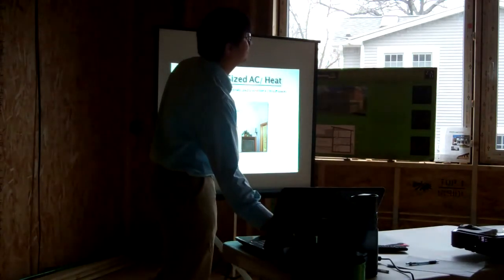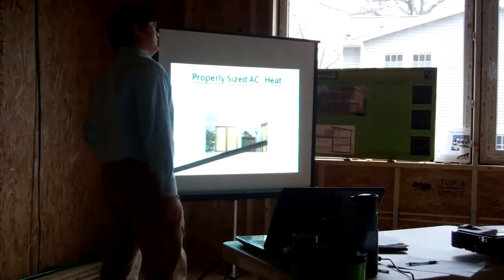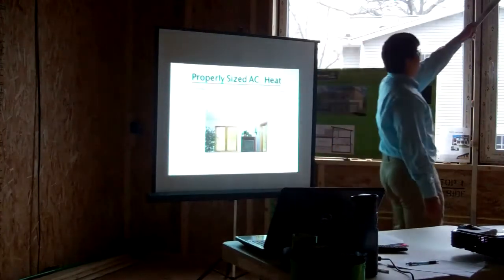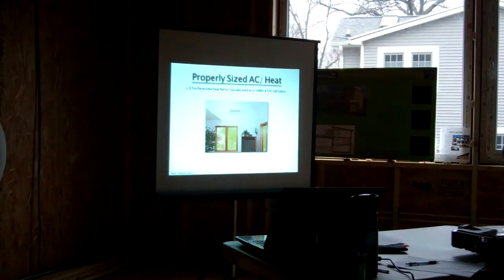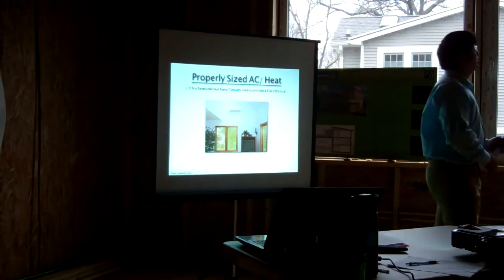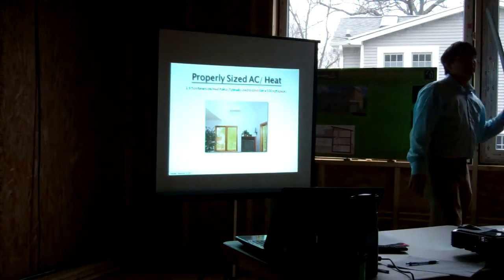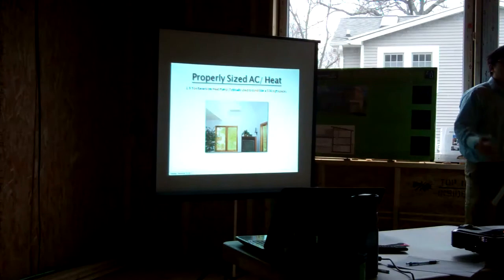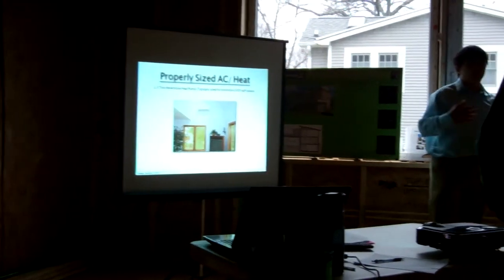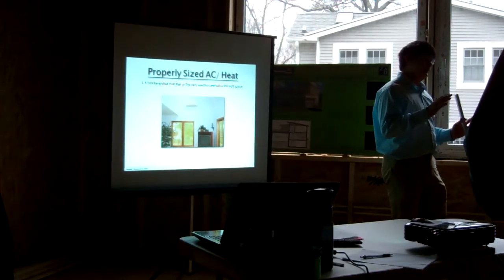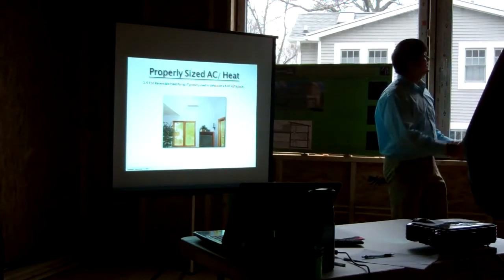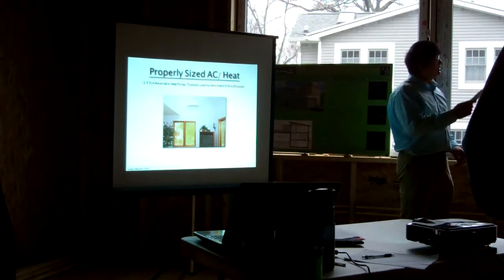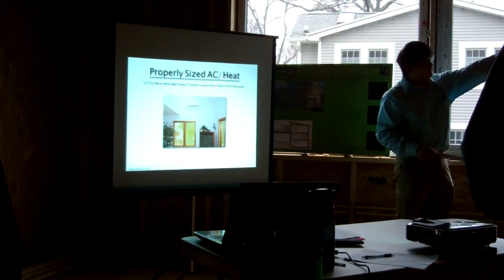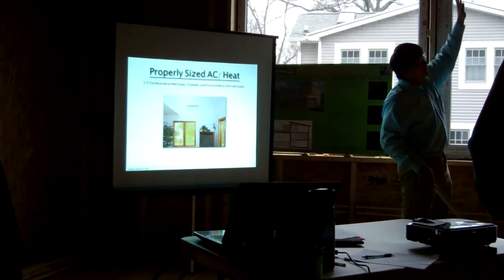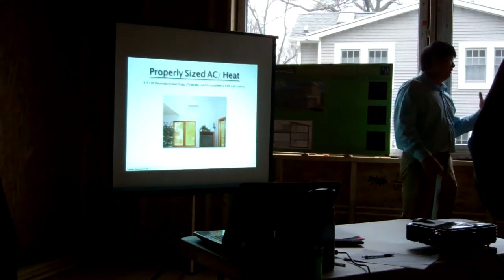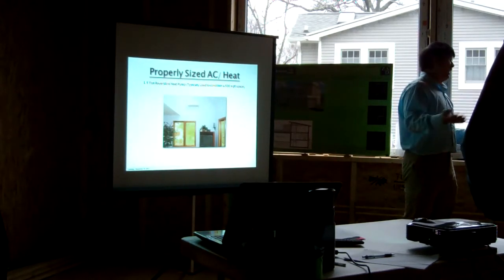What are these, part of that? That's a good question - but these are transfer fans, to allow air to go upstairs. You see them in every single room. The reason we put this is because sometimes at night, when you close your bedroom doors, there could be temperature stratification, a difference of maybe 10 degrees or so. So this is an insurance policy: as conditioned air blows out from that mini split, this will suck it directly into the rooms and supply it, so it'll also ventilate the entire house this way.